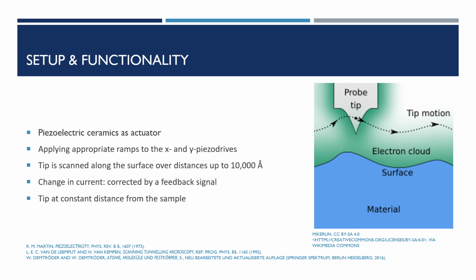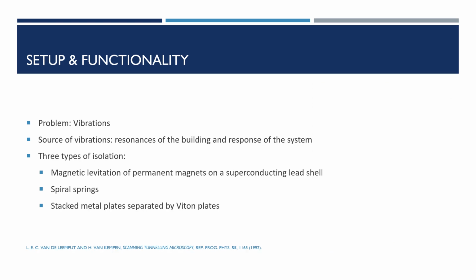Besides the constant current mode, there are further modes, like for example the constant height mode. An advantage of this is that it can scan faster, even produce real-time images, but there is also the risk of a collision with the surface of the sample. You can also do spectroscopy, which was the original idea of Binnig and Rohrer. As already mentioned, vibrations are one of the technical challenges that had to be overcome. An important source of vibrations are resonances of the building where the scanning tunneling microscope is located, but also sound and the response of the system to these disturbances.